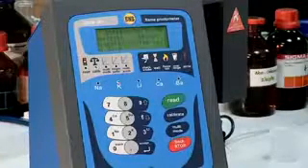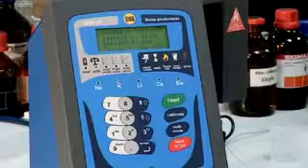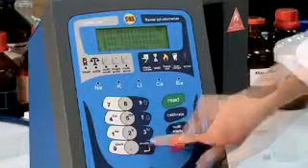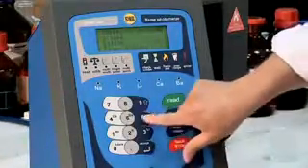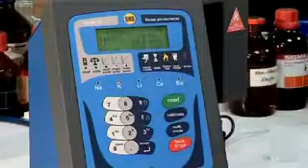An exciting feature of the BWB XP is the calibration correction. Flame photometers are known to drift over time due to temperature changes and flame setting changes, and as a result, often need to be calibrated. The calibration correction will shift the entire curve to remedy the change. A multiple points curve can be corrected by aspirating just one solution, a real time saver.